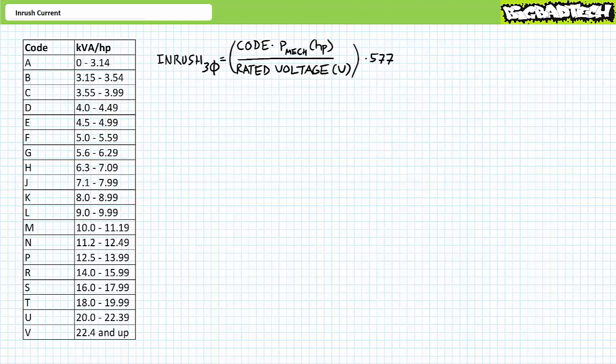Full voltage — sometimes called direct online or across the line motor starters — must be designed to make inrush current. Inrush at times is an unwanted phenomenon that may affect the performance of other electrical devices in the same distribution system. If you've ever experienced the lights dim in an old kitchen upon starting up a blender or a vacuum cleaner, this is the result of inrush.